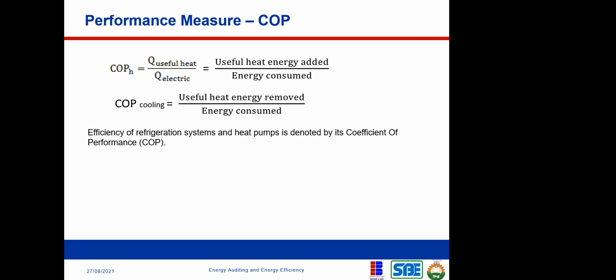And what does coefficient of performance mean? It simply means the useful heat. Remember that the essence of having your heat pump is to generate heat from your atmospheric air. It collects the atmospheric air and uses it to generate heat for you, right? So the useful heat that you get from that heat pump, all over the electric power that it draws to operate, we give you what we know as coefficient of performance. That is COP for short.